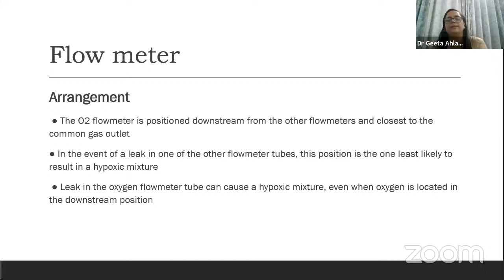Internally, it is always positioned downstream and close to the common gas outlet, because this is just a small effort to prevent any kind of hypoxic mixture delivery in case there is any leakage in the pipe. Still, there can be leakages further downstream, but this is the maximum that can be done to prevent it: it should be kept downstream and nearer to the common gas outlet.